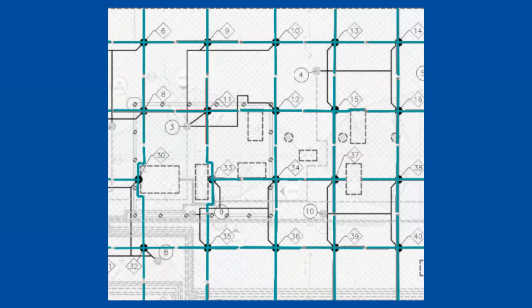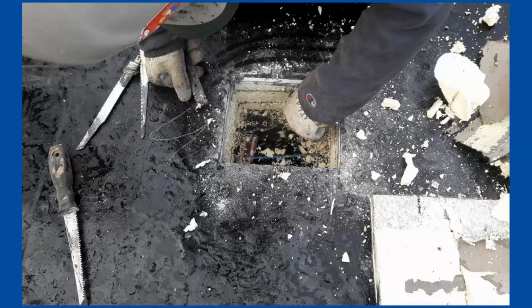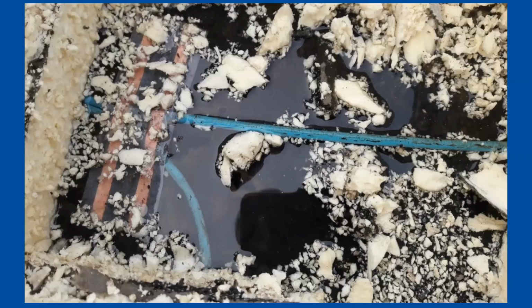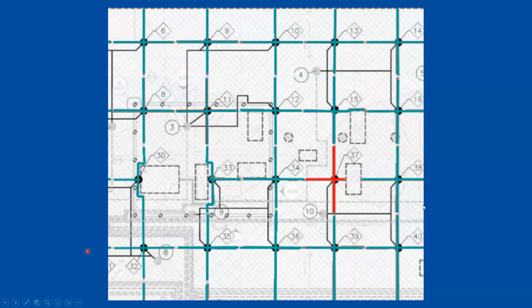It was Thanksgiving weekend, and the project manager received an email that one zone had gone into alert. 15 minutes later, the system pulls another set of data. 2 additional zones went into alert. 15 minutes later, another zone. After that long weekend, contractor showed up on site, cut into the assembly, and there was standing water on the vapor barrier. The system indicated the source began around this HVAC unit, and there was a time frame.